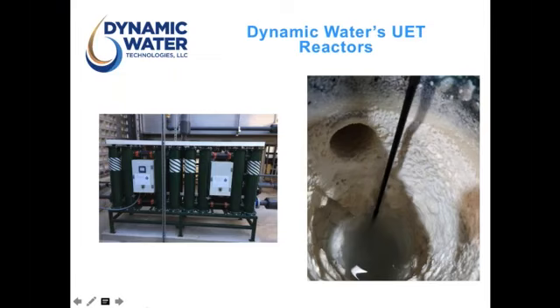So here's a picture of what the system looks like on the left here. Essentially this is reactor-based technology. What you see here is 16 reactors that we divert water from your recirculating system into and through the reactors and out the bottom. And if you look at the picture on the right, that is a picture inside one of the reactors. You see the rod in the center of the reactor there. That is an anode that creates an electrical current. And so what happens in that reactor constantly as water's flowing through it is we are creating free chlorine in the system itself. Most chemical treatment programs operate by feeding chlorine from chemicals outside the system and into the system. We are creating it ourselves from electrolysis and the chlorides in the water.